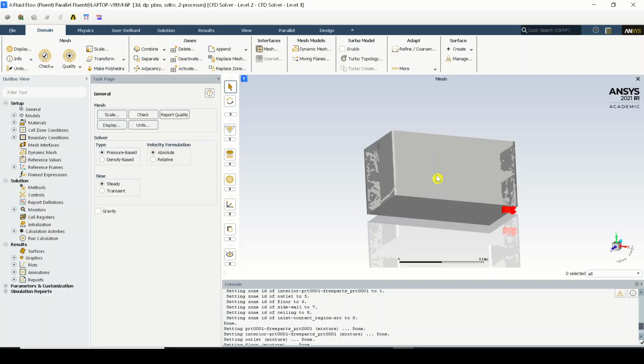And the flow field variation depends on the positions of your heat sources as well. So on a general note, we never think into much detail whenever we are planning to set up our rooms, right? We don't really think where the inlet must be, where the heat sources must be positioned. If you have continuous circulation happening in a room, then that will eventually create air which has an older age. That means it is staying in the room for a very long interval of time, and air which is staying for a longer interval of time will be contaminated, obviously, because occupants like us humans generate carbon dioxide. I mean, we emit carbon dioxide.